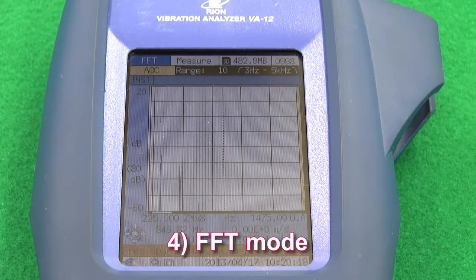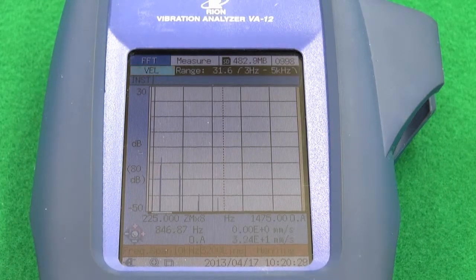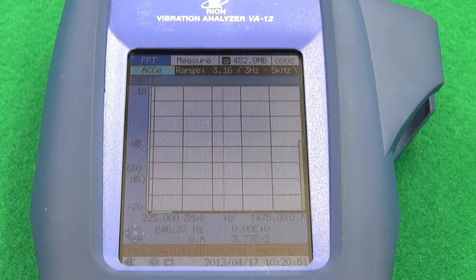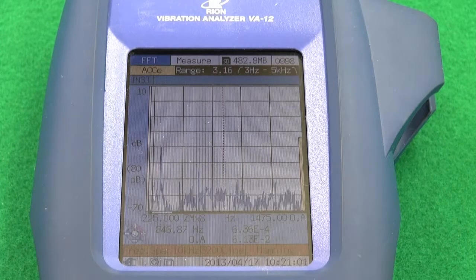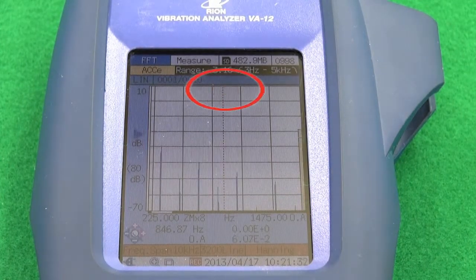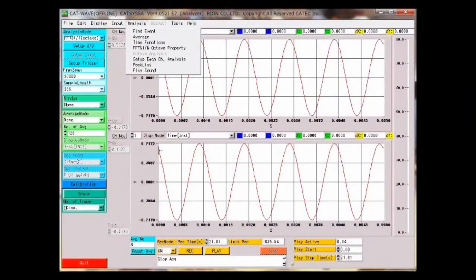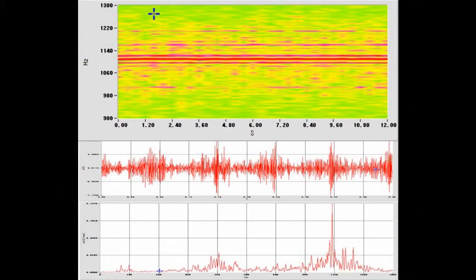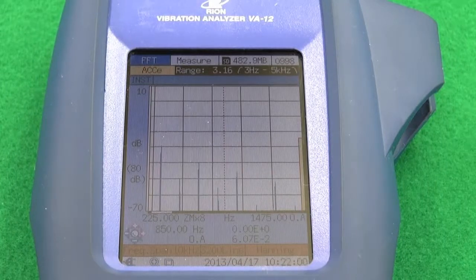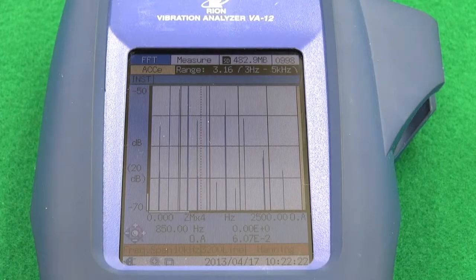Feature 4: FFT mode. In FFT mode, an acceleration envelope is often used for detecting bearing faults. In this mode, acceleration, velocity and displacement can be displayed with up to 3200 spectral lines, making it possible to measure at a high frequency resolution. Therefore, vibrations can be detected which have occurred within a narrow frequency band. Wave files can be recorded; the duration is dependent on bandwidth — up to 10 seconds at 20 kHz bandwidth or 2000 seconds at 100 Hz bandwidth. Using dedicated analysis software, host processing can be done using waveform file data from the VA-12. You can listen to the vibration sounds and judge and analyse them. The frequency axis can be magnified 2, 4, 8 or 16 times, and the magnitude axis can be magnified up to 1024 times in FFT mode.